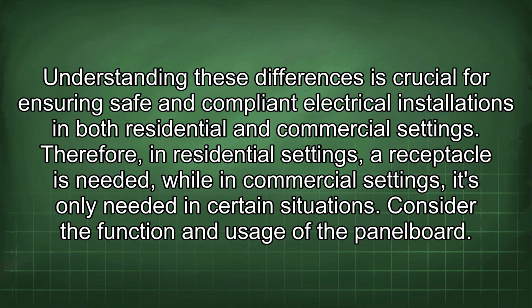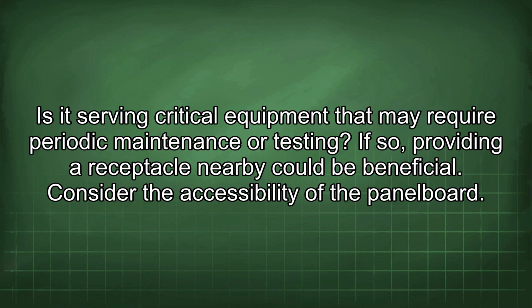Understanding these differences is crucial for ensuring safe and compliant electrical installations in both residential and commercial settings. Therefore, in residential settings, a receptacle is needed, while in commercial settings, it's only needed in certain situations. Consider the function and usage of the panel board. Is it serving critical equipment that may require periodic maintenance or testing? If so, providing a receptacle nearby could be beneficial.